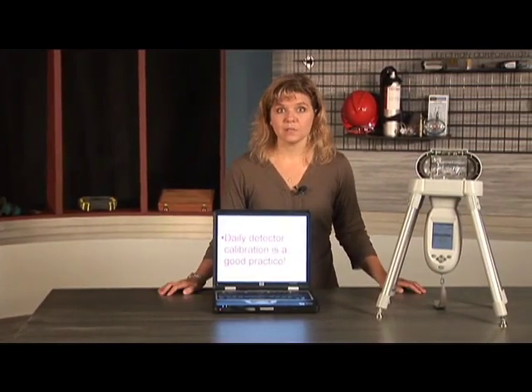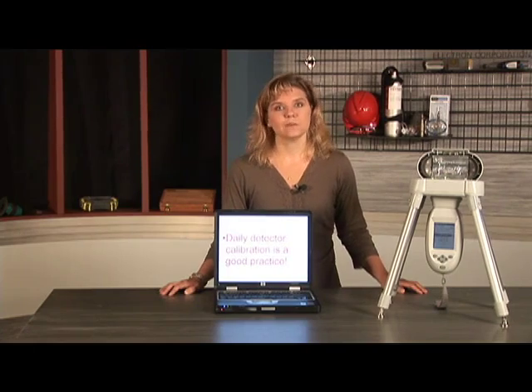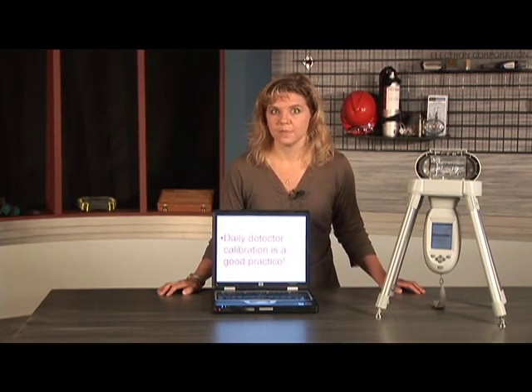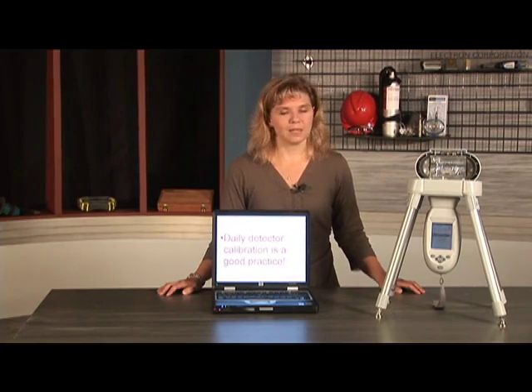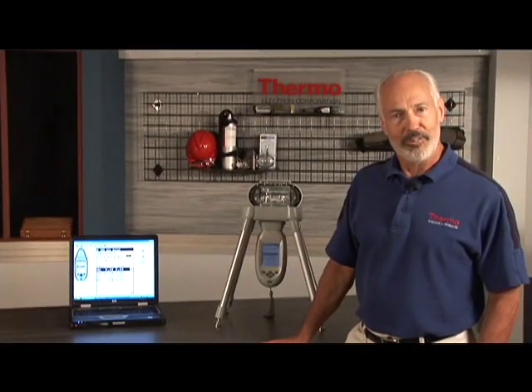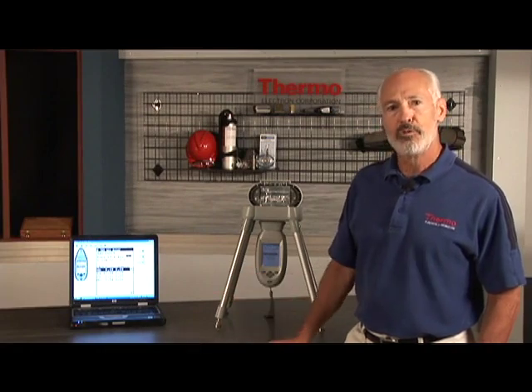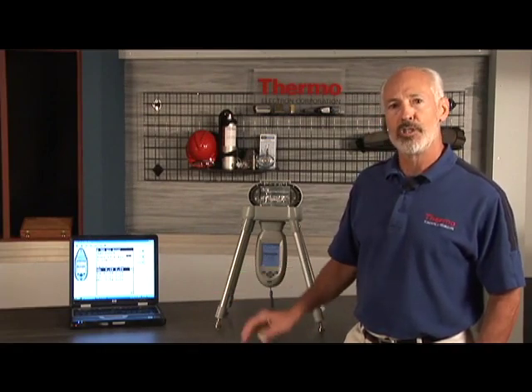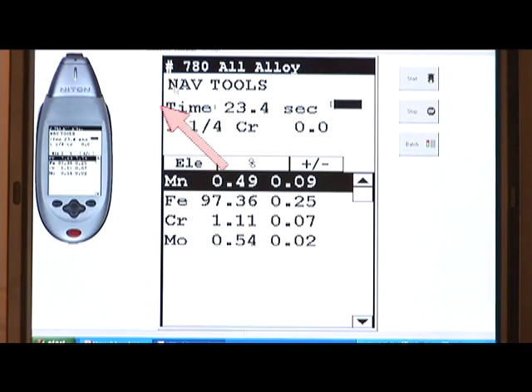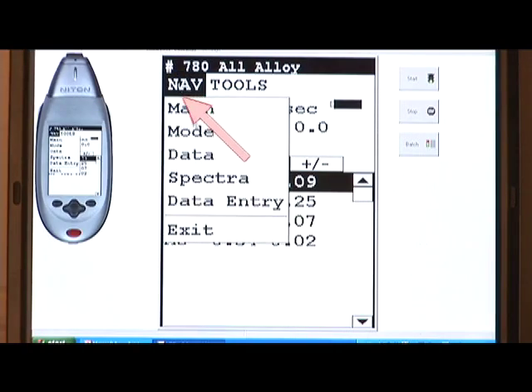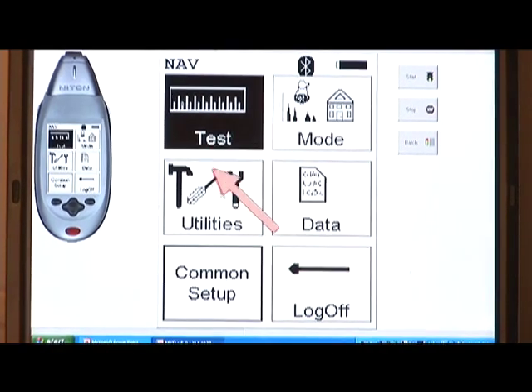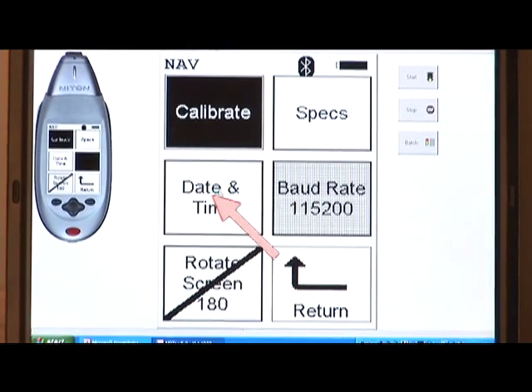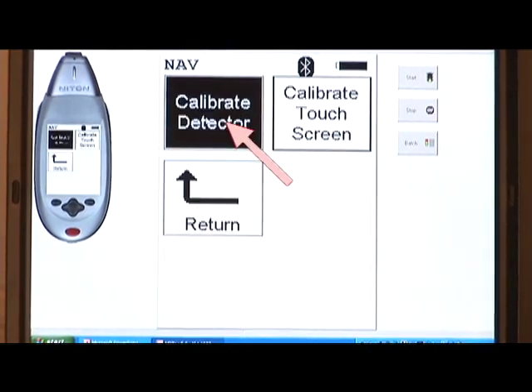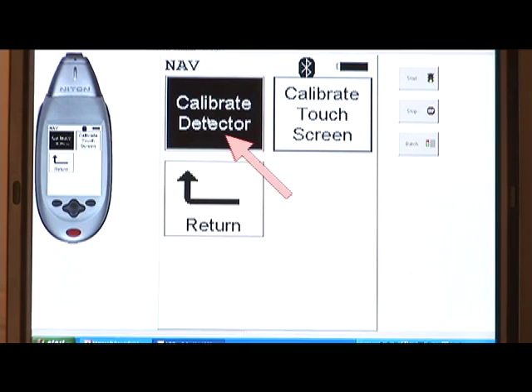In addition, some modes, such as lead-based paint, will require you to do a detector calibration each time you turn your instrument on. We are now going to show you a detector calibration. I'm going to take you through the detector calibration now. Because we're hooked up via Bluetooth wireless, we'll perform and show the results on the PC. From the results screen, we select the navigation menu. From the list of options here, we select the main menu and then utilities. From the utilities menu, we select calibrate. From the calibrate menu, we can select the calibrate detector option.